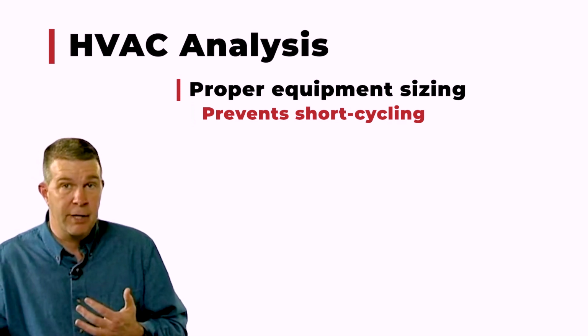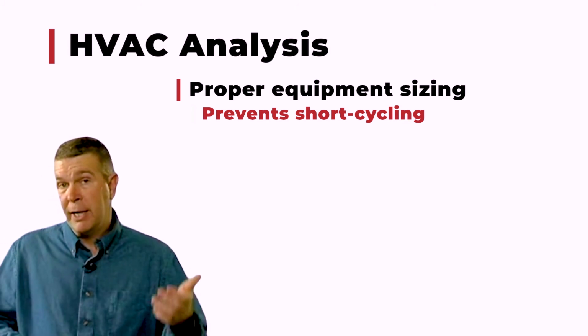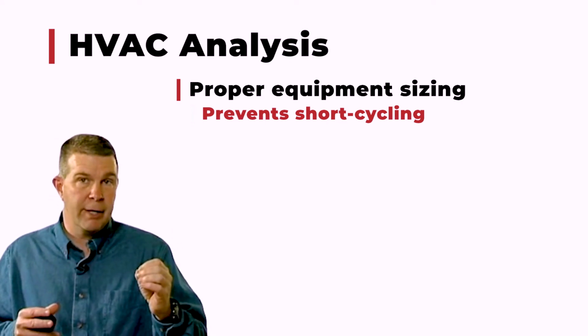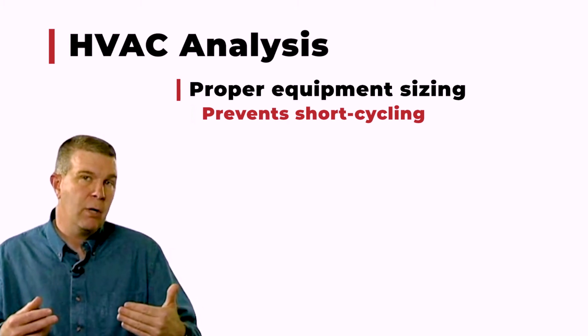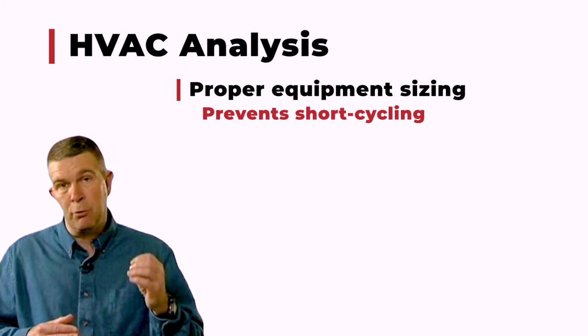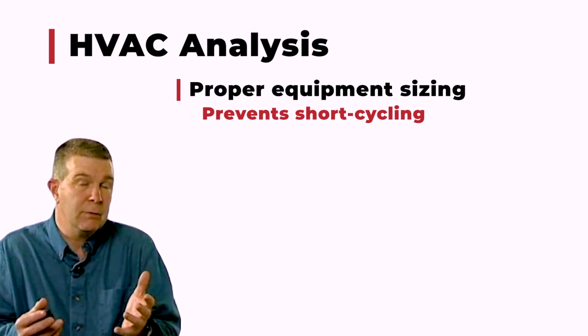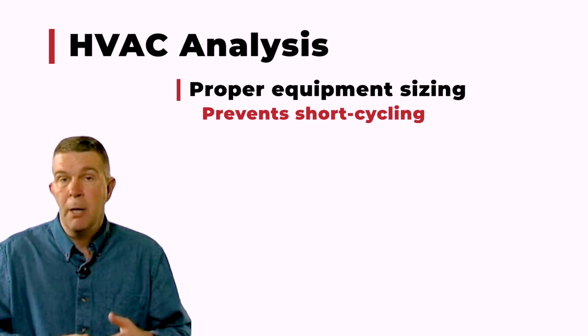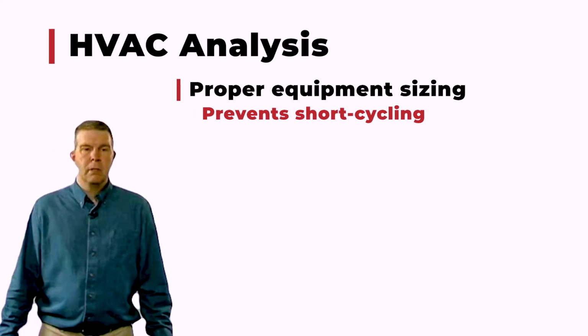And we know what an elevated humidity level does to us because we talked about it back in the building science chapter. As the humidity level goes up, it might conspire to find those areas that you may not have properly sealed or that maybe allow that high humidity to come in contact with a cold surface, and you've got a dew point. That dew point is condensation, and that condensation is a callback for you when it's really not your fault. It's the HVAC contractor using rules of thumb and putting in systems the way he's always put them in because he was used to putting them in houses that weren't as energy efficient and tight as the one that you just built.